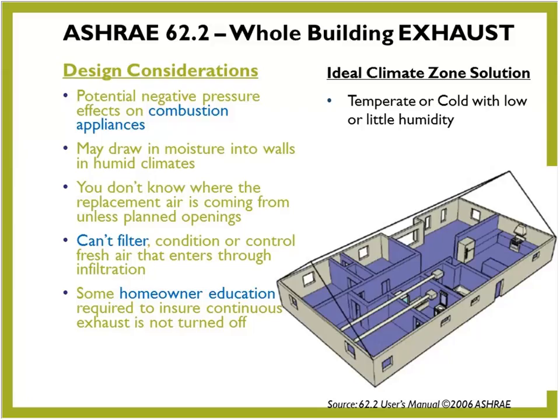As I mentioned, one of the criticisms of the exhaust-only approach is that we can't filter that air because it's not coming through a duct like it would with the supply or the balanced ventilation. It's not coming through a duct. It's leaking through the building shell. There's studies that show that air coming in through the building shell and the insulation and whatnot actually acts like a MERV 9 filter, but it's not as desirable, let's say, air coming in as you would through a duct. So, you know, again, that's one of the criticisms.